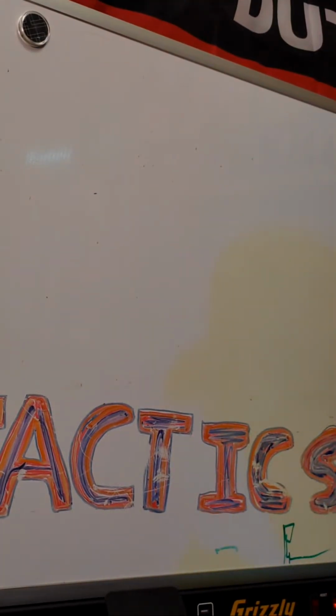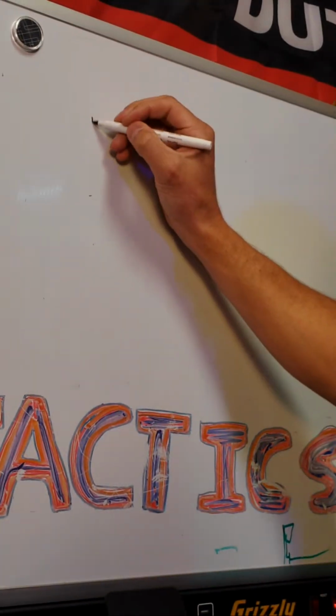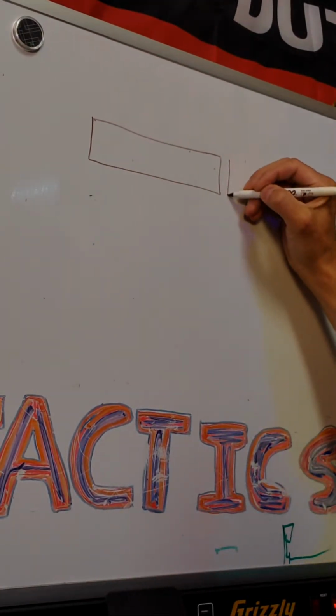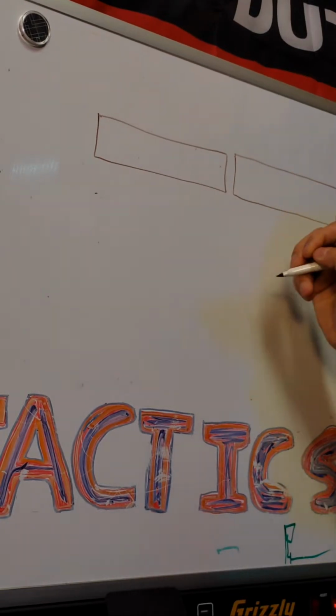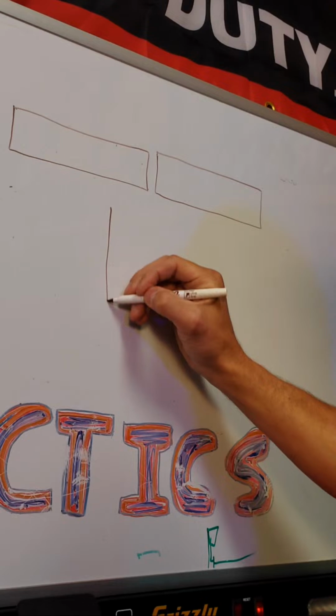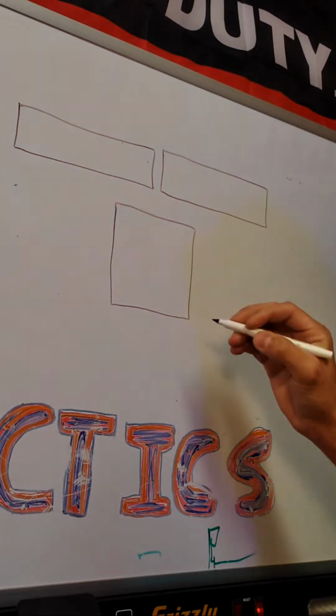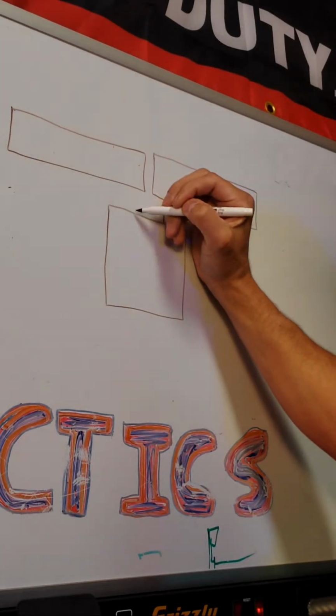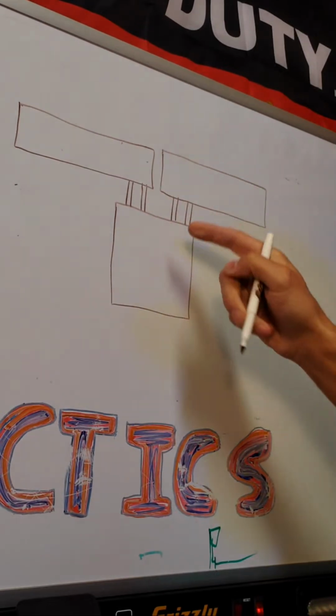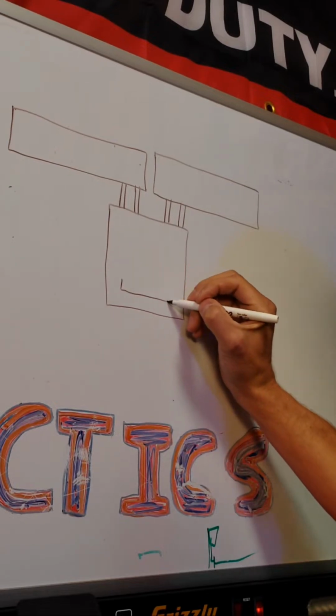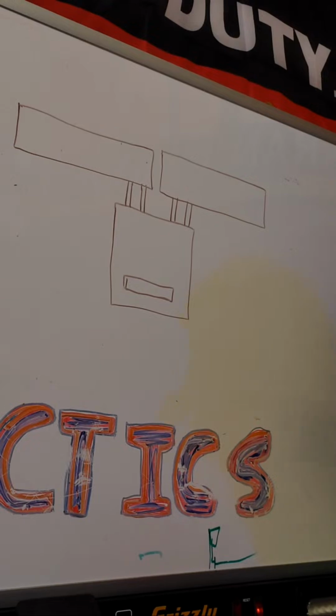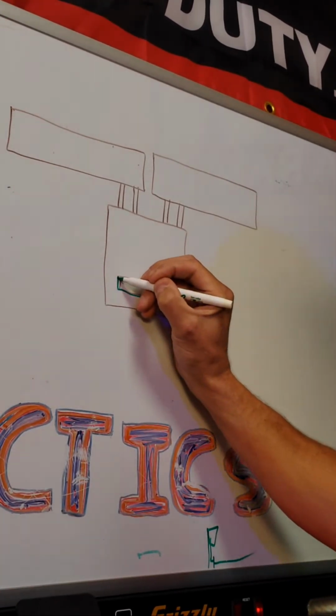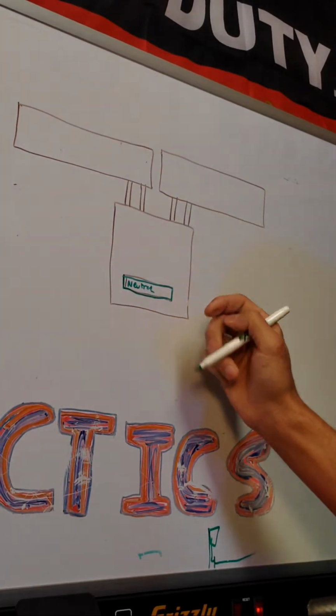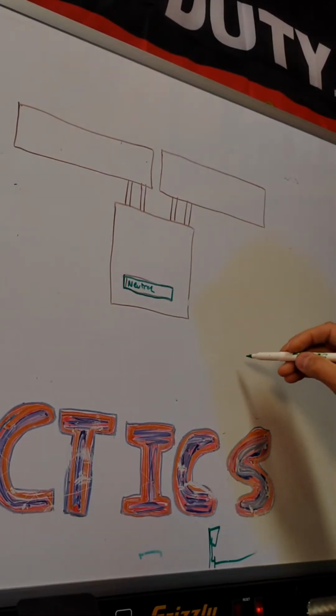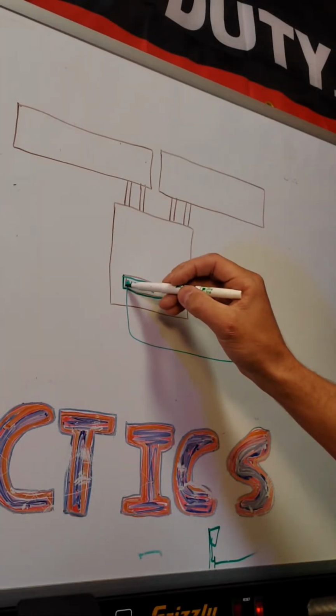Well, that's what these guys did, but I'm going to show you how they royally messed it up because they thought that one number 4 was going to be good for everything. So in this case, they had 2 gutters overhead. Okay. And they had the tap can down below. And they had 2 pipes here. And 2 pipes here. This is that bar that we talked about. This is the neutral bar. I'm going to draw it in green. Essentially the neutral. Same thing, grounds, neutral, same thing at the source, right? They ran their UFER to this neutral bar.